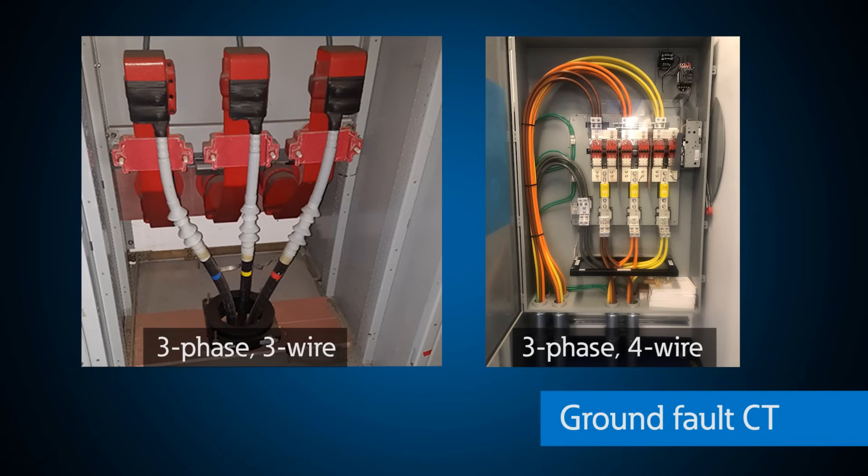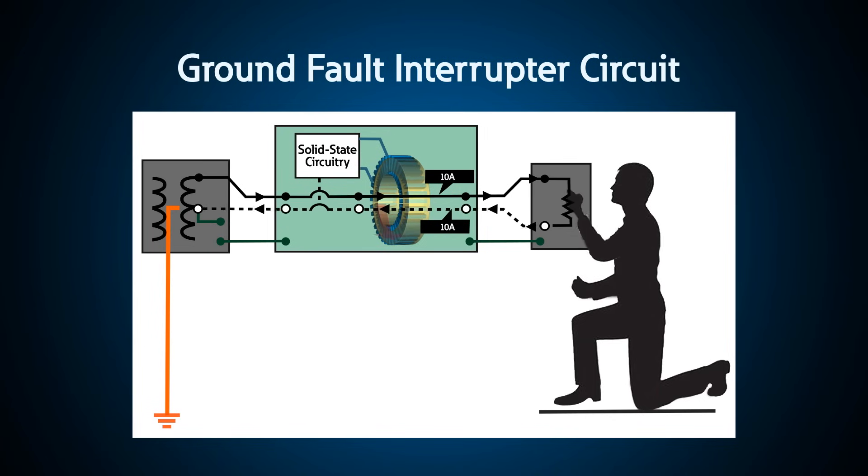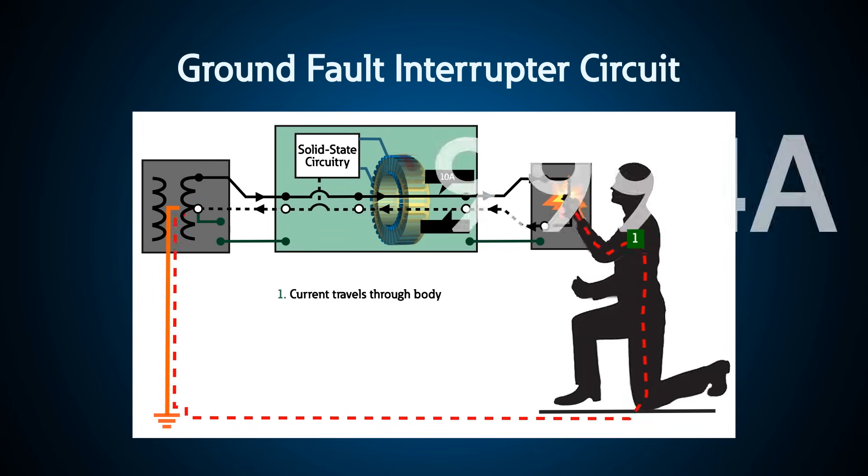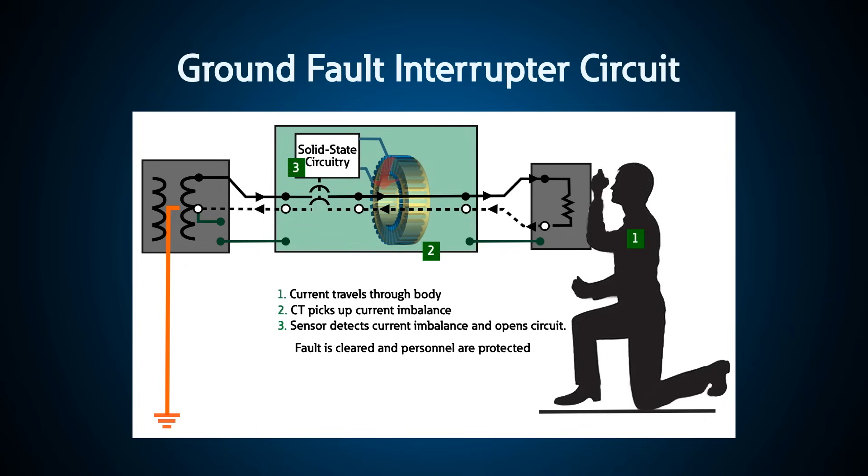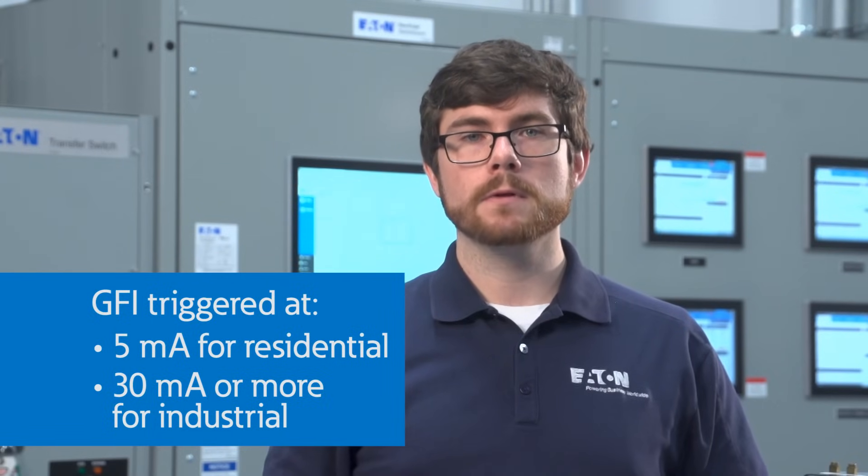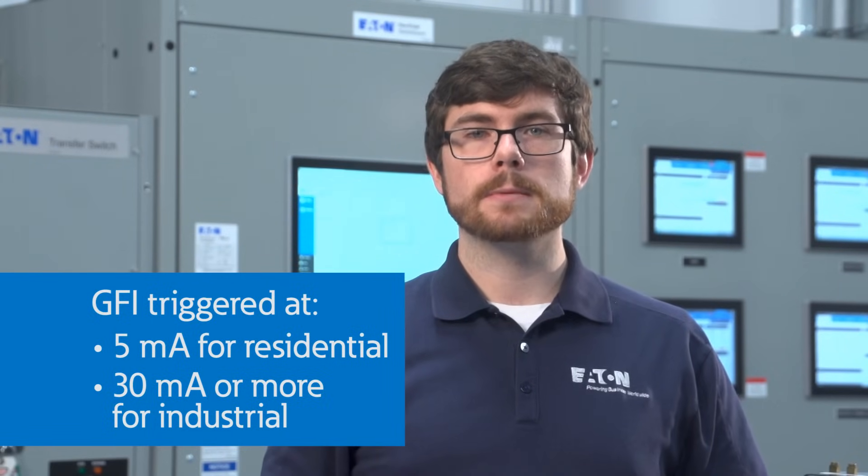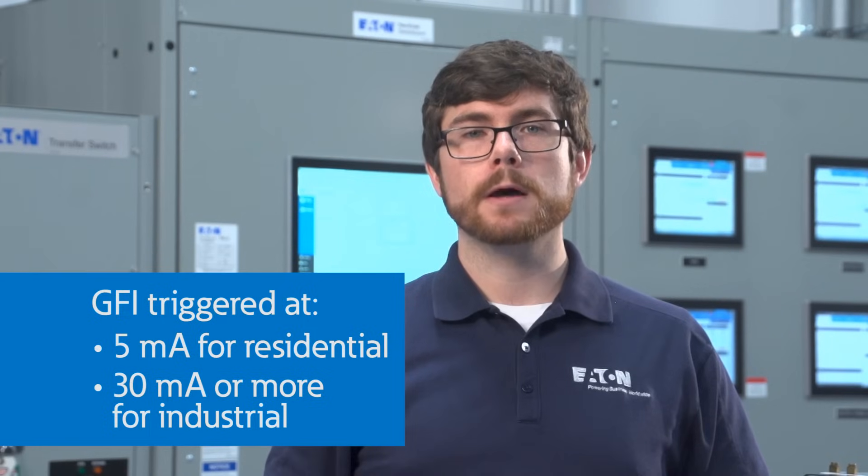All of the phases and neutral conductors go through the ground fault CT and if any residual current exists, in other words, current comes in on one of the phases but doesn't return on the other phases or neutral, then there is a ground fault. In your house, this is triggered by a 5 milliamp level and industrial plants, this may be 30 milliamps or even a couple hundred amps. Ground fault protection is generally for personnel safety in homes and equipment protection in industrial applications.